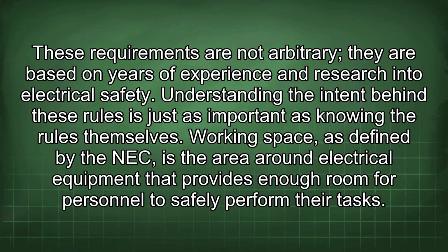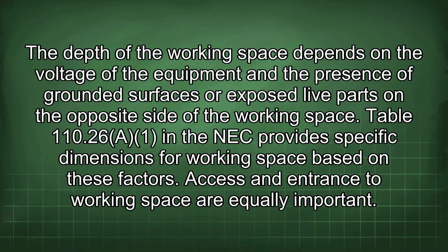Working space, as defined by the NEC, is the area around electrical equipment that provides enough room for personnel to safely perform their tasks. The depth of the working space depends on the voltage of the equipment and the presence of grounded surfaces or exposed live parts on the opposite side of the working space. Table 110.26(A)(1) in the NEC provides specific dimensions for working space based on these factors.